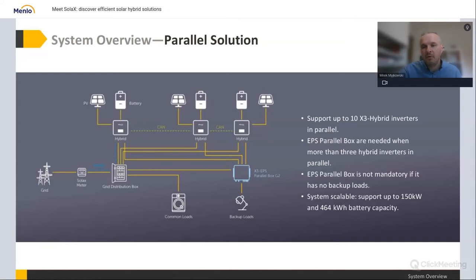When we have over 3 hybrid inverters in a parallel system, the EPS parallel box should be used. There are 2 types: a smaller one, up to 60K or up to 6 units—whichever comes first—and a bigger one, up to 150K and up to 10 units. So you can choose between these 2 EPS parallel boxes.